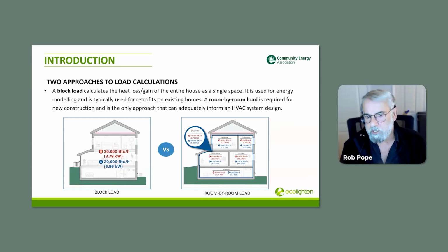So there are two approaches. A block load is the whole house. It calculates the heat loss and gain of the entire house as one single space. Despite how many rooms there are, it just takes the shell of the building and the total heat loss and heat gain of that building.